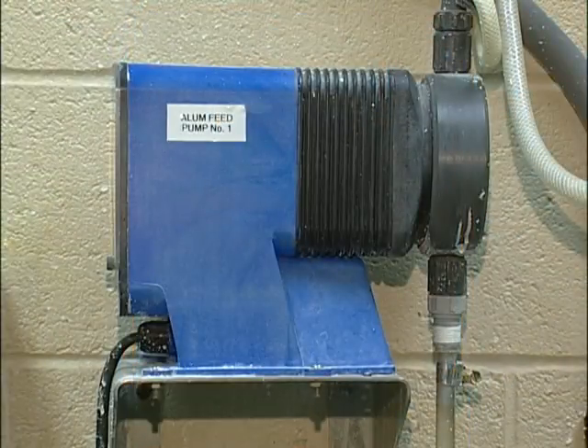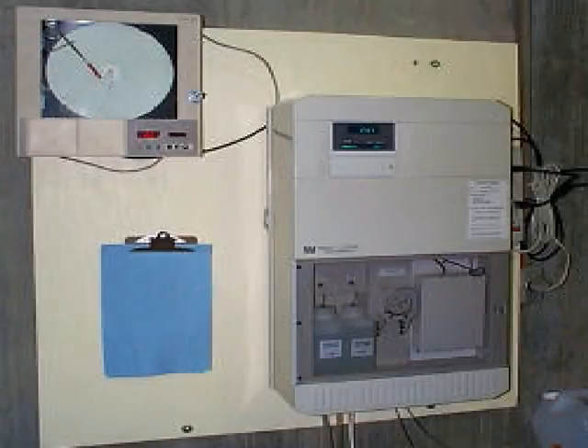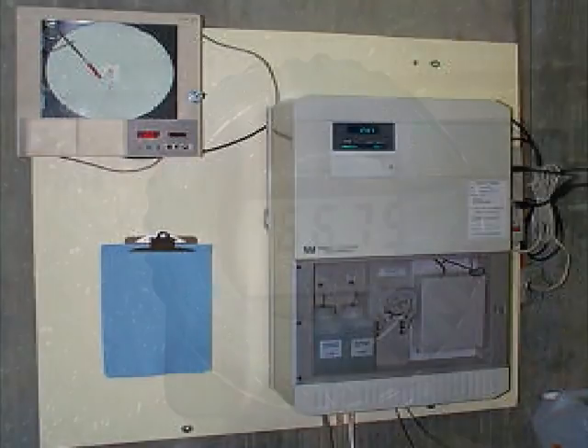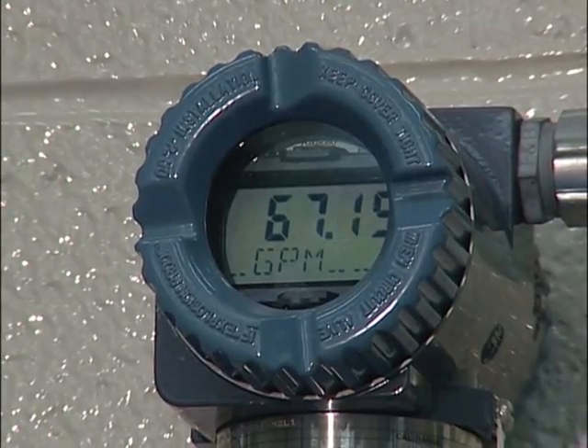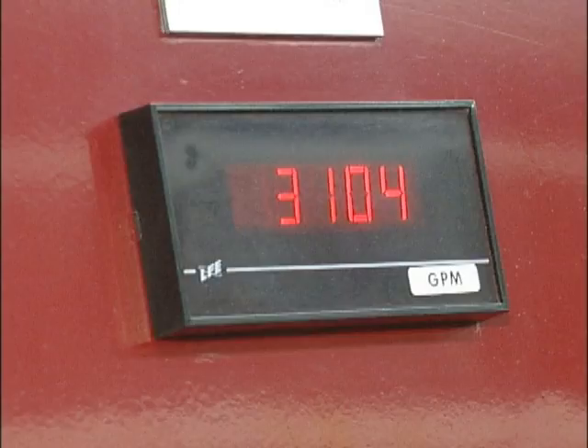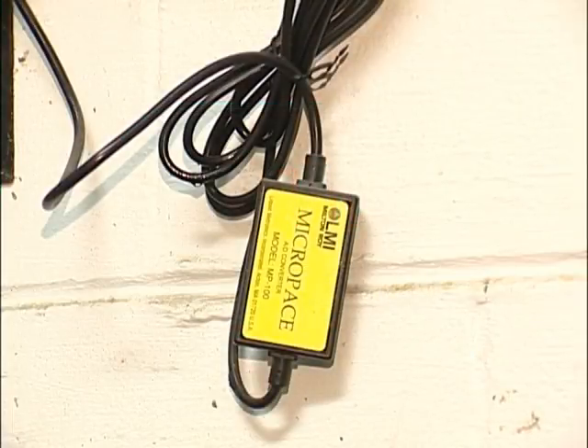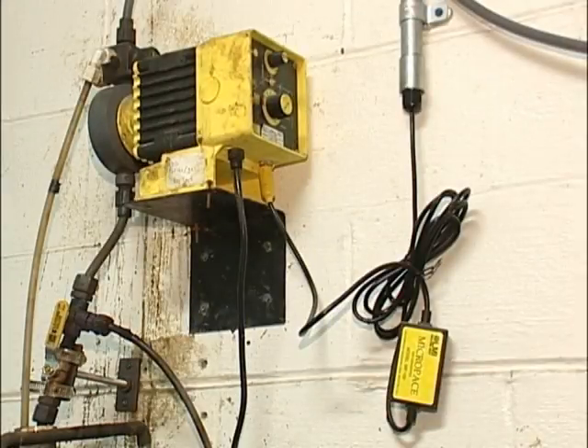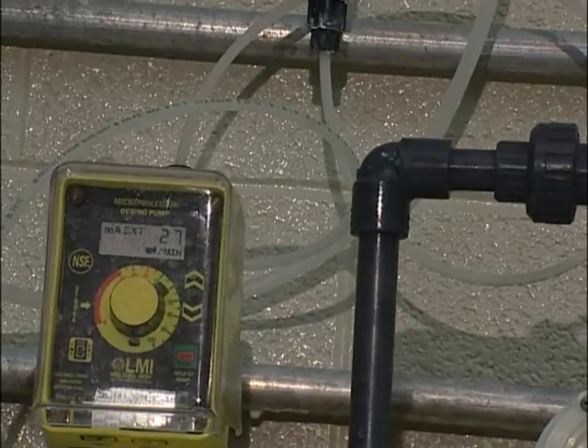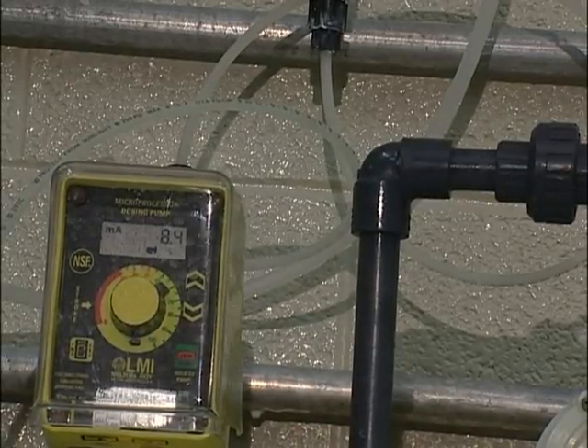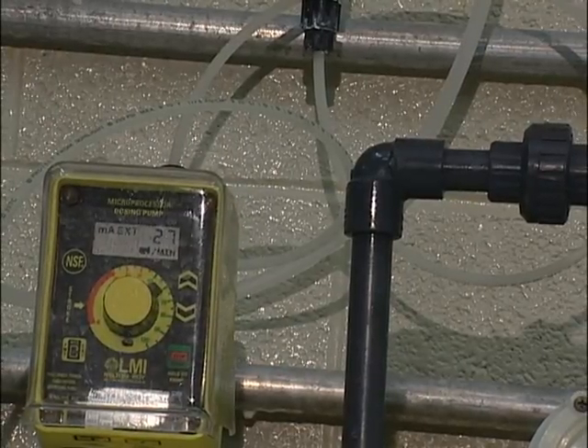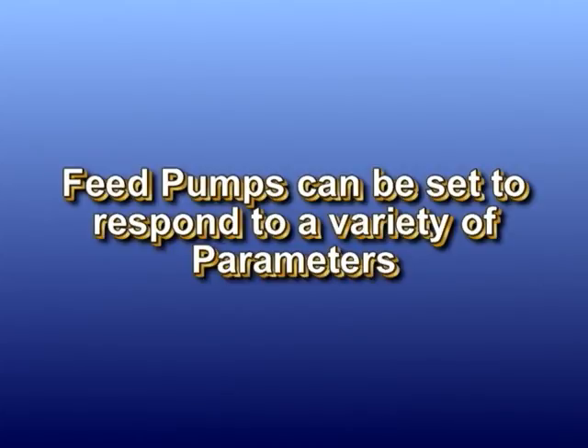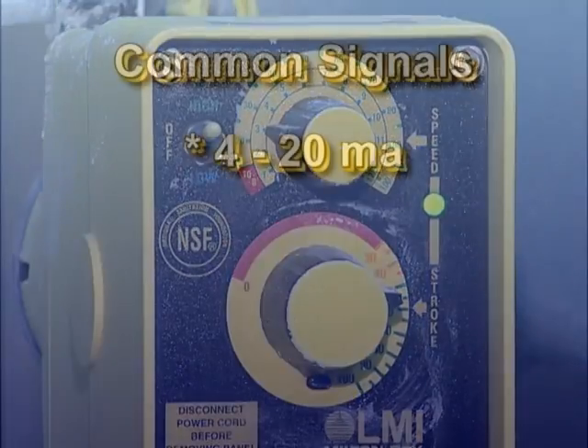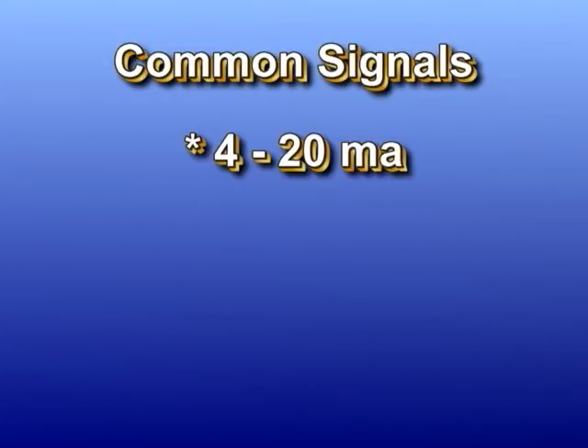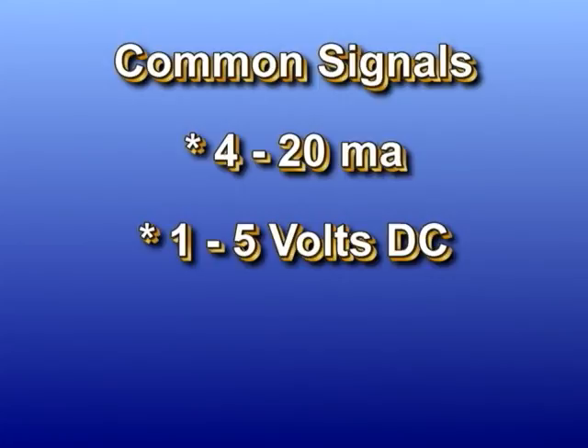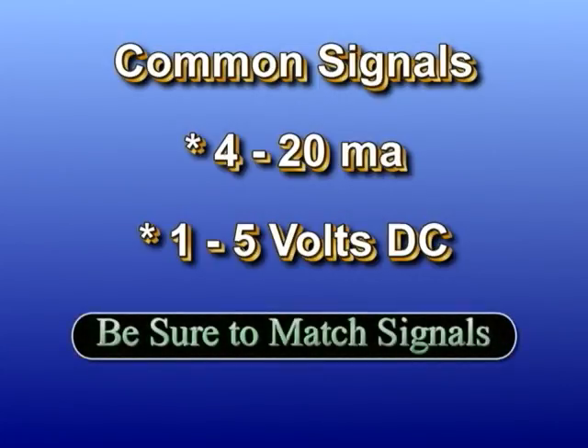Some pumps are set to pump a fixed amount whenever they are in operation. Others can be set to respond to varying input signals to yield differing amounts in response to changing conditions. For example, pumps can be flow-paced, so they vary delivery rates with changing flow rates. A sensing unit picks up the rate of flow and sends a corresponding signal to the chem feed pump, delivering more chemical for higher flows and less for lower flow conditions. Some pumps can be programmed to respond to signals set in a prescribed range. Some pumps run off a 4 to 20 milliamp signal, while others respond to a DC current of 1 to 5 volts. The operators should be careful to match the signals from the sensors to the pumps.